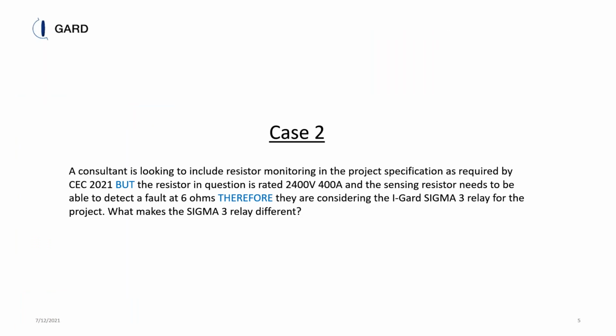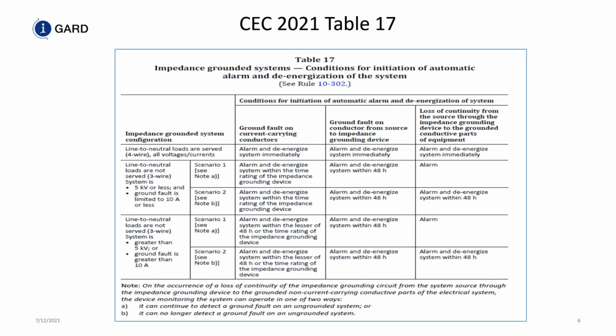So case number two: a consultant is looking to include resistor monitoring in a project specification as required by the Canadian Electrical Code 2021, but the resistor in question is rated 2400 volts, 400 amps, and I assume 10 seconds. And the sensing resistor needs to be able to detect the fault at 6 ohms. Therefore, they are considering an I Gard Sigma 3 relay for the project. What makes the Sigma 3 relay different? In order to discuss this, we need to look at the changes in Table 17 of the Canadian Electrical Code.